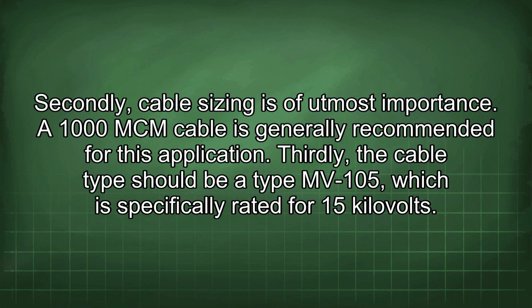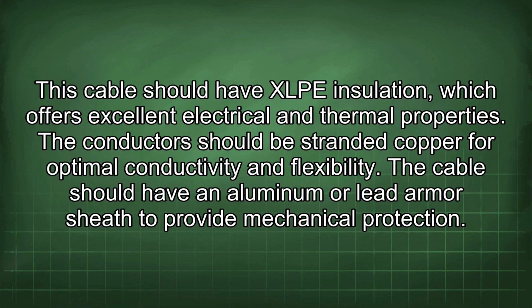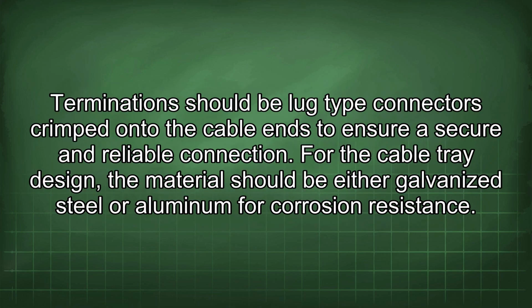Thirdly, the cable type should be a type MV-105, which is specifically rated for 15 kV. This cable should have XLPE insulation, which offers excellent electrical and thermal properties. The conductors should be stranded copper for optimal conductivity and flexibility. The cable should have an aluminum or lead armor sheath to provide mechanical protection. Terminations should be lug-type connectors crimped onto the cable ends to ensure a secure and reliable connection.